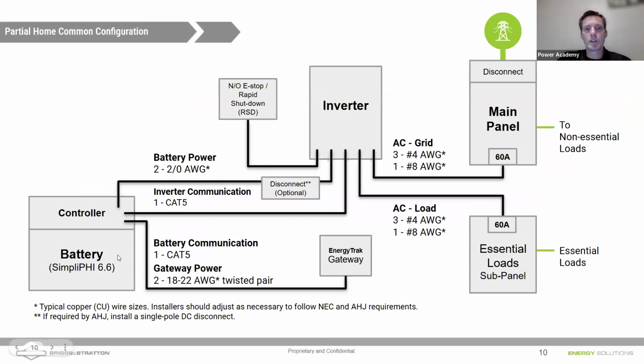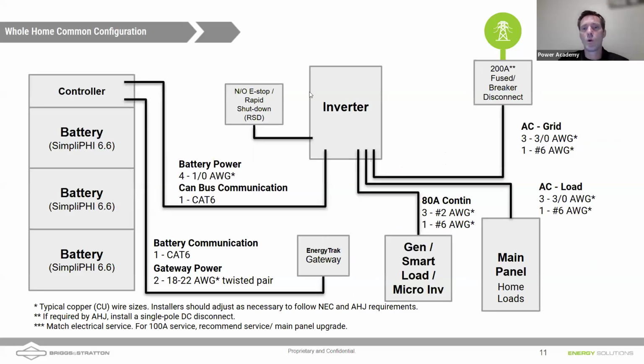Wiring looks very similar on the DC side, bringing the power from the batteries into the inverter. Of course, you want to have a rapid shutdown set up on your inverter, and then you might also have solar, either AC or DC coupling through the inverter. Whole home, looking at a wiring diagram similar to this. This is just with a single stack of batteries. You can also have multiple stacks of batteries if you do have longer duration outages, or you've got more solar, more loads on the home. Maybe you want to keep that AC running for a long time in a hot, humid place.